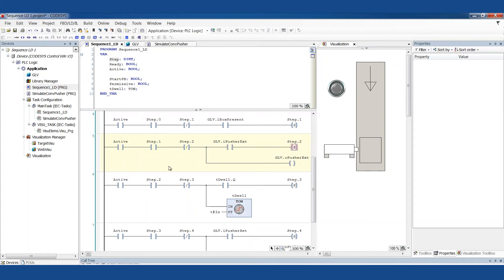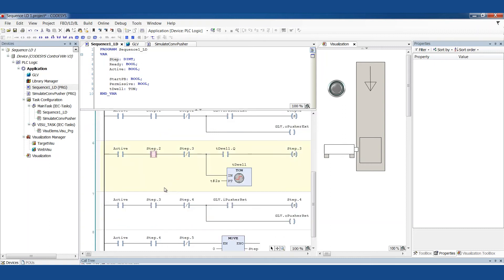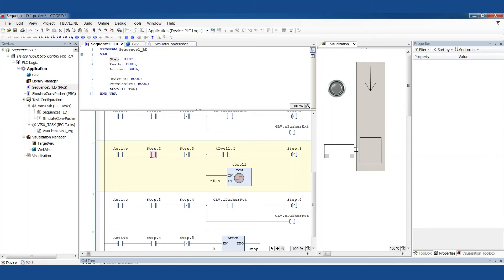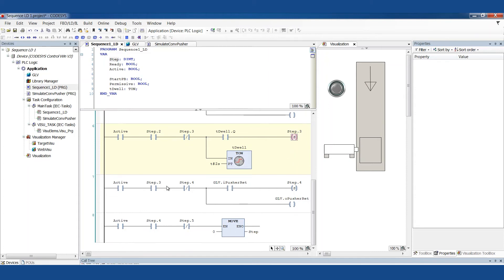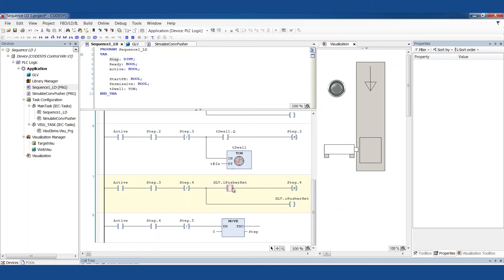So we told the pusher to extend. We found that it got there. Now we're ready to go to step two. We set step two. Here we are in step two. Now we're going to set a dwell timer. I put this two second timer in here just so that it will wait at the extended position so that we can see that this light lights up, this cylinder sensor. It's not really necessary for the physical process we're trying to model here. When that timer is done, then we can go to step three. When we get to step three, we're going to fire another output. This is the retract output to try and bring this cylinder back in. We're going to wait until that gets there. We've got a sensor that tells us that it got there, and we go to step four.